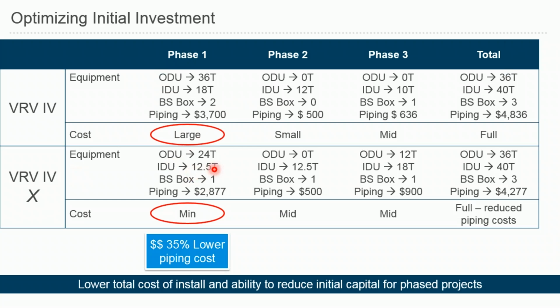Versus with VRV4X, especially at the initial stages of the project, that's giving you a lot of flexibility and cost reduction because for the outdoor unit capacity, now you're down to a dual module configuration, 24 ton. The amount of indoor unit capacity that you need to get to the 50% connection ratio is much less than the original configuration. Instead of installing 18 tons of indoor units, now you're down to 12 and a half tons. And when you look at the piping sizes, you're seeing a reduction there as well, about 35% lower piping costs over here.